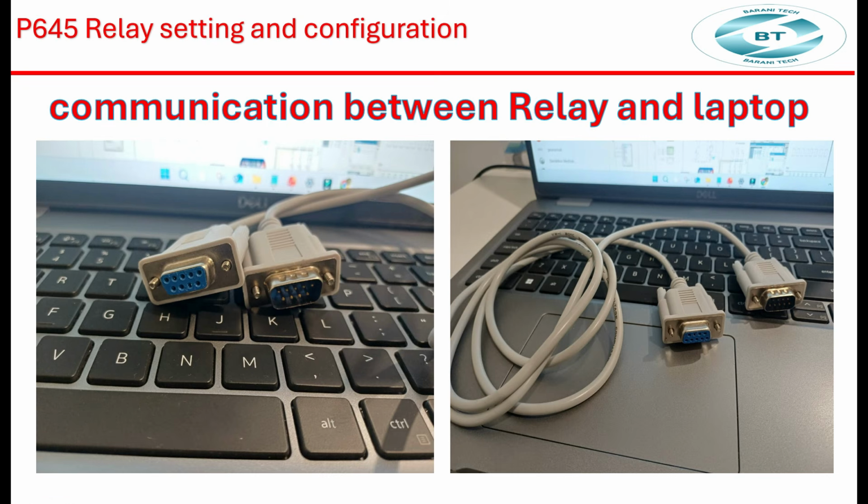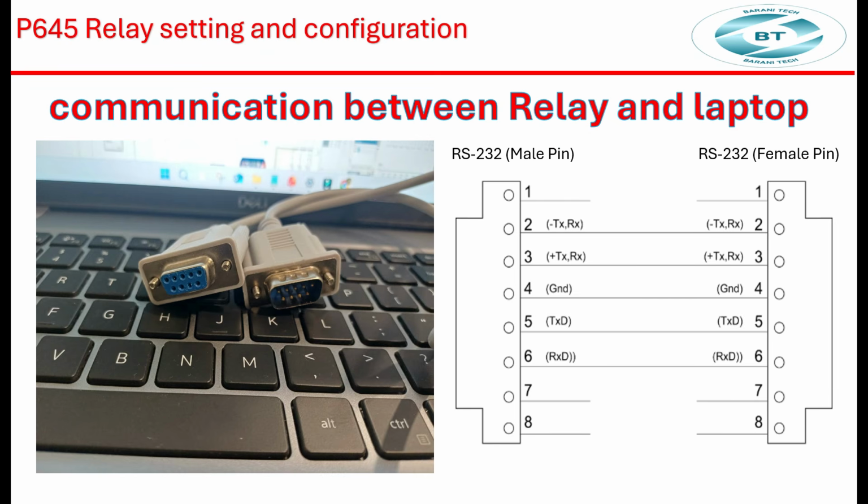Part 1, Establishing Communication. First things first, let's look at how to get your laptop talking to the relay. The first thing you need is the correct communication cable. If your laptop has a built-in RS-232 port, you can use a standard RS-232 straight cable. However, most modern laptops don't have this port, so you'll likely need a USB to RS-232 converter cable.